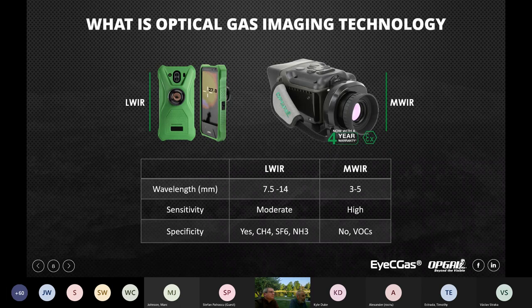To summarize the two OGI technologies: the uncooled is a long-wave camera with moderate sensitivity — you're able to see medium to large leaks, usually from a closer distance. The EyeCGas 2.0 is the cooled camera, mid-wave, very sensitive, and you're not limited to specific gases — you're able to detect over 400 compounds, also from a further distance.